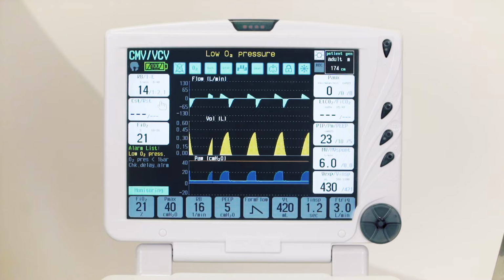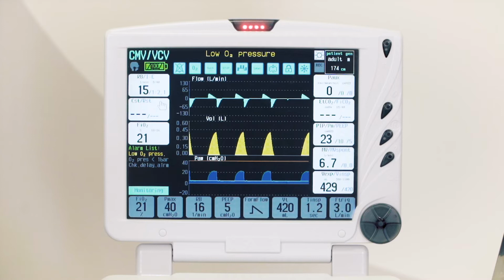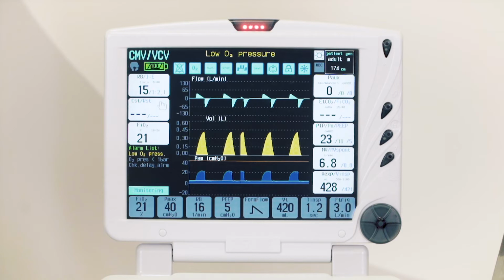The device has an FiO2 electrochemical type sensor. Its lifetime depends on oxygen environment time and oxygen concentration. At medium operation parameters, FiO2 sensor lifetime is more than 1.5 years. Calibration of the FiO2 sensor is important in the final phase of the sensor life cycle to extend its lifetime and accuracy.